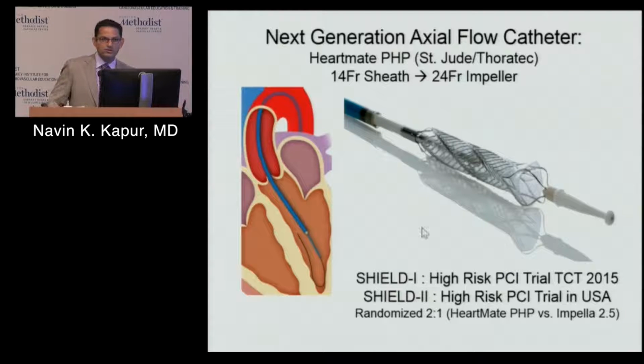As you deploy this across the aortic valve, you unsheath this impeller blade up to 24 French, and you can get flows on a bench up to about 8 liters per minute. So you're essentially putting in, through a much smaller arterial incision, the equivalent of a 5.0 plus type device. SHIELD 1 is a high-risk PCI trial that was presented at TCT. SHIELD 2 is the multi-center study we're doing in the U.S., which randomizes patients to PHP versus Impella 2.5 for high-risk PCI. But of course, the major potential advantage of the PHP device is related to its use in cardiogenic shock, where you can really get these patients unloaded effectively.